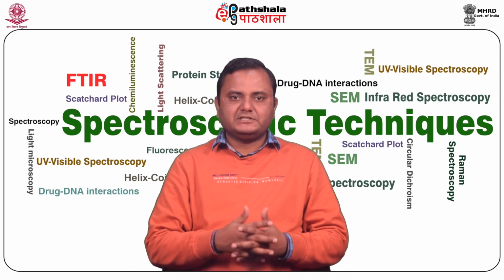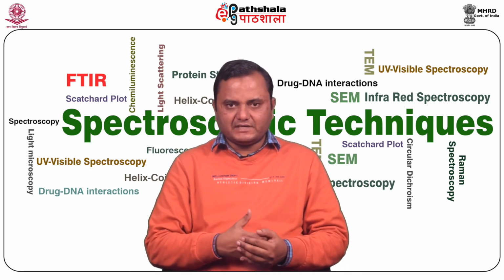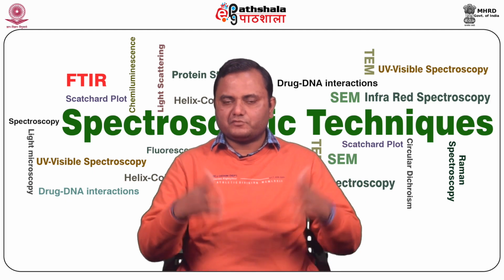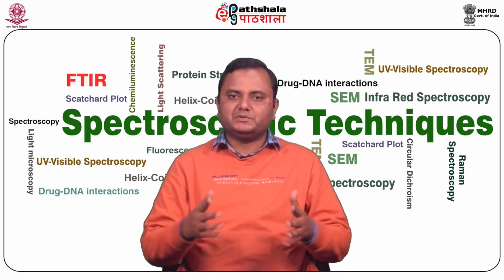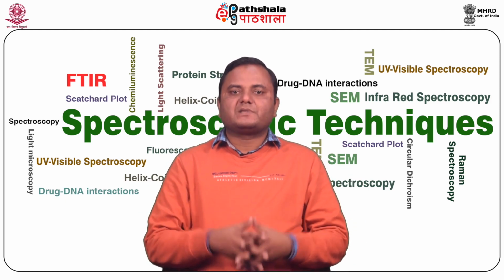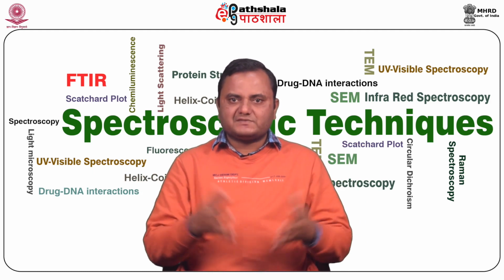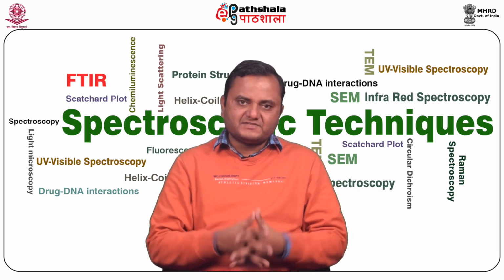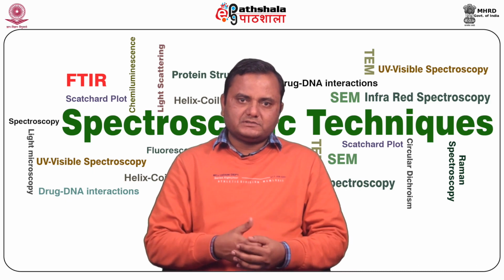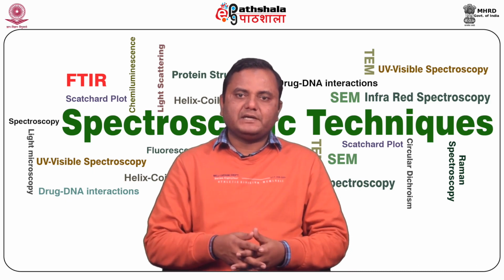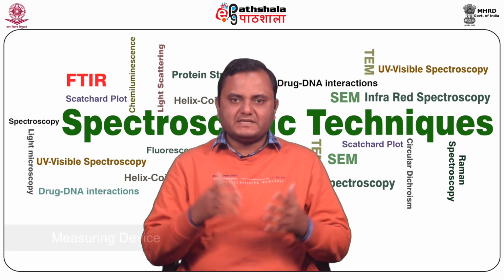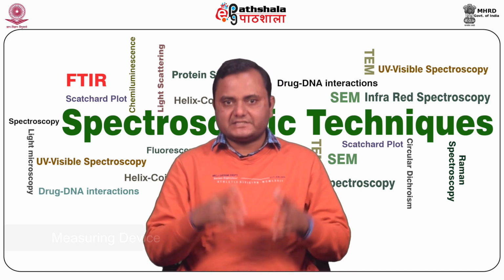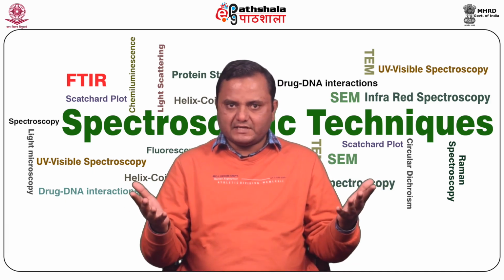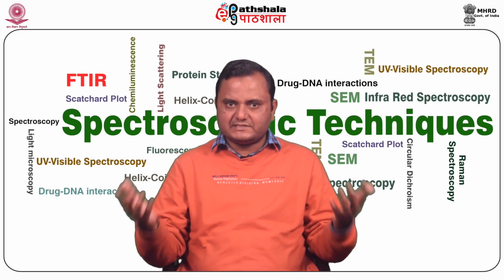Photomultiplier tubes serve as a detector to measure the intensity of the light. Because the light quantity is very low, the photomultiplier tube helps you multiply the light and give you a proper amount of signal, and the output current of the photomultiplier is fed to a measuring device that indicates the extent of fluorescence in the form of a signal or in the form of a fluorescence spectrum.